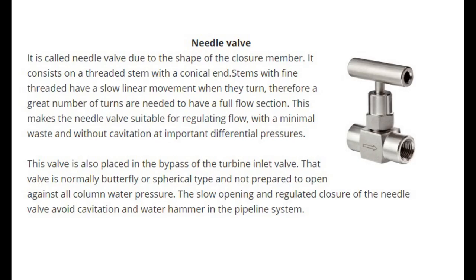The needle valve is named due to the shape of its closure member. It consists of a threaded stem with a conical end; stems with fine threads have a slow linear movement when turned, so a great number of turns are needed to achieve full flow. This makes the needle valve suitable for regulating flow with minimal waste and without cavitation at important differential pressures. This valve is also placed in the bypass of the turbine inlet valve, and the slow opening and regulated closure of the needle valve avoid cavitation and water hammer in the pipeline system.